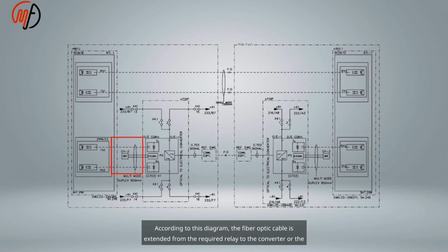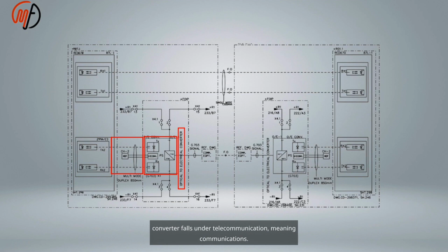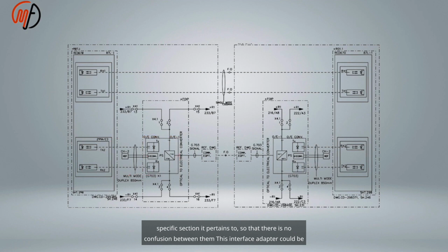According to this diagram, the fiber optic cable is extended from the required relay to the converter or the interface adapter, which may also be called the communication interface unit, to convert the optical signal into an electrical signal. The purpose of this converter is to create a separation or segregation between the different sections of the station. Therefore, it acts as a boundary between telecommunication engineering and power engineering. From the side of the relays to the converter itself, it falls under power, while everything after the converter falls under telecommunication, meaning communications. The purpose of this segregation is to precisely identify the location of the problem and to determine which specific section it pertains to so that there is no confusion between them.